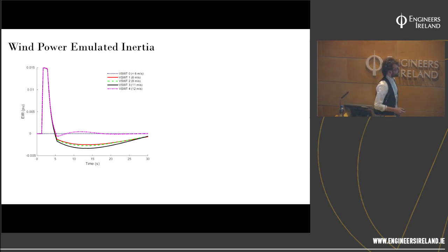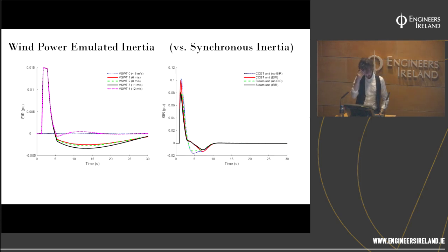So you can see that the recovery of the wind turbine changes with wind speed. Now I'm going to contrast that with a synchronous inertial response. So this is a CCGT and a coal-fired unit. I suppose the two things to note is that this moves, and it is umbilically linked to the frequency, as I said. This is related to the rate of change, the df/dt of the frequency. So this will move automatically with the system frequency, whereas this response here is decoupled from the frequency.